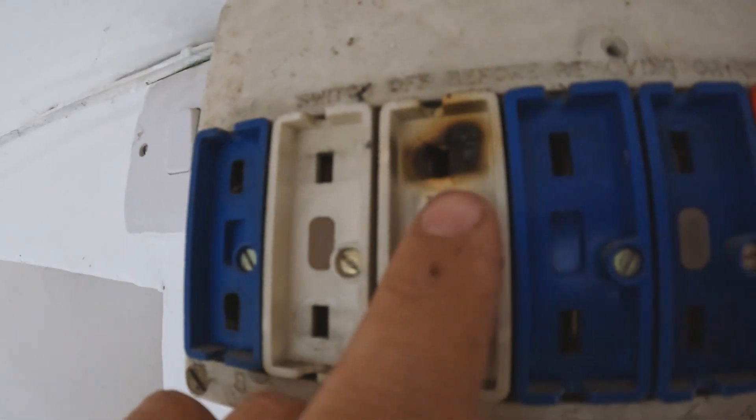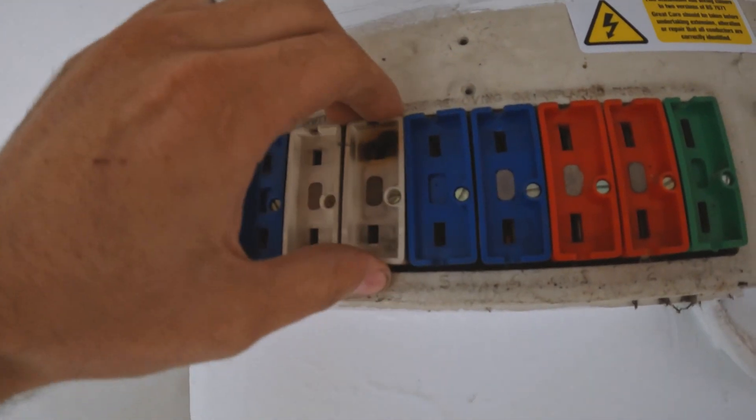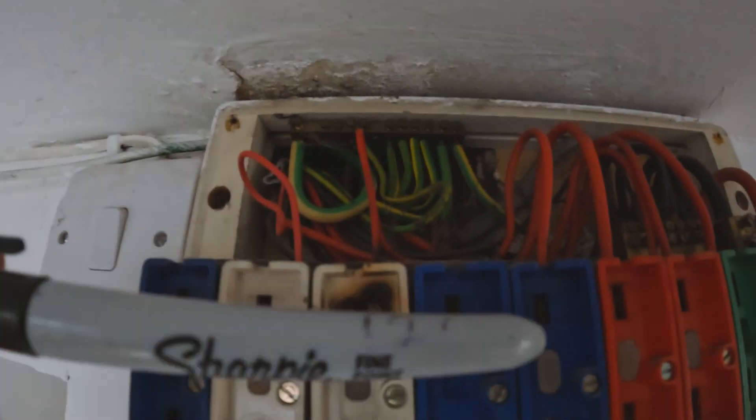This is why you get your electrics checked — look at that, it's all gone crispy! It's probably loose connections in there causing it to heat up, and you can have a fire. So what I'm going to do is tidy this up.